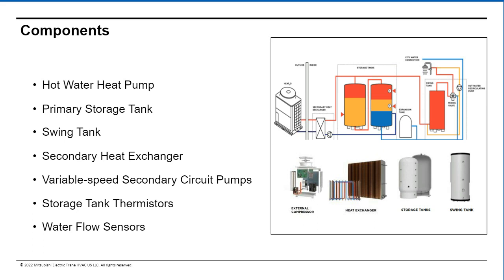Next is a swing or maintenance tank on the far right here you can see, and this is really what we're using to take care of our recirculation load in the building. So most, if not all, commercial buildings today have hot water recirculation to give better response time to the space. And what this swing tank is set up to do is just maintain that load on the system. And what we've put together for the marketplace is a full package of all these different components, as well as a control offering to make this as easy to implement into the marketplace as possible.